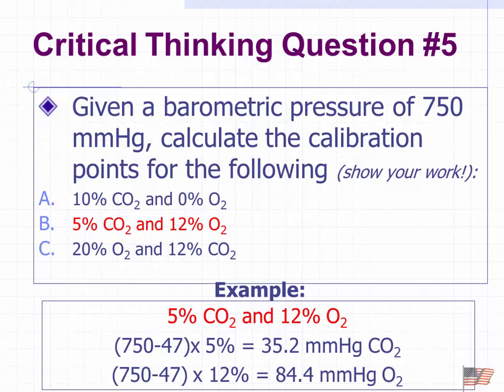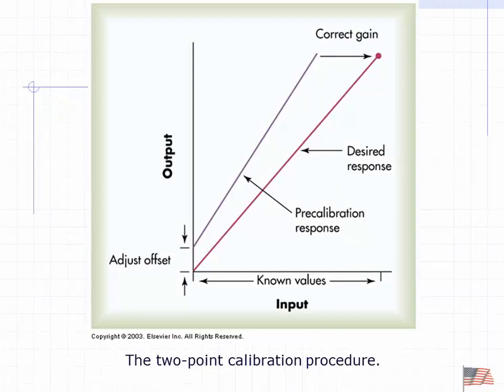Right? Just by multiplying barometric pressure times the fractional concentration of the gas that I'm using, I can determine the partial pressure. We're going to use that then to calibrate it, because it's going to find a line there, that purple line that shows what the pre-calibration response is. So this is what the measured value is seeing now for that percent of gas. It knows that the red line is where it needs to get to.